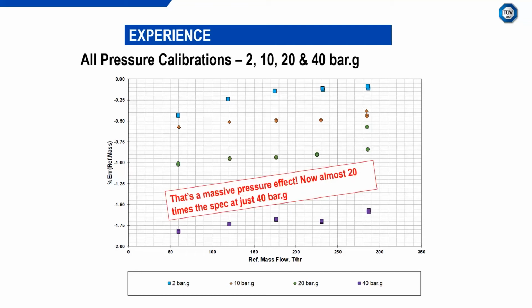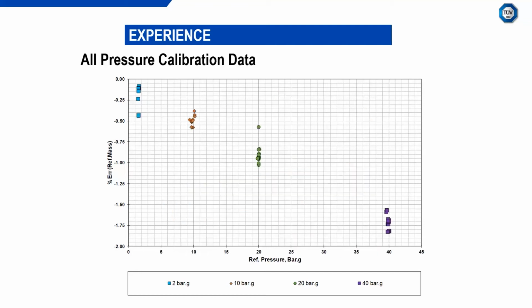40 bar, relatively high pressure, but not extremely high pressure for liquid. And you're under reading by 1.75%. So that's very significant. Now, if I show this data, this is still the same data, but now I'm just showing you the results presented with respect to reference pressure, so bar gauge on the x-axis as opposed to flow rate. You can see that it's linear. So you can see there's a linear effect, which is good news. If it's linear, it's easily correctable.